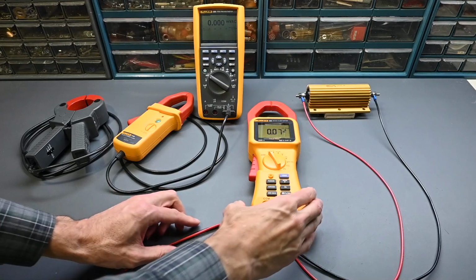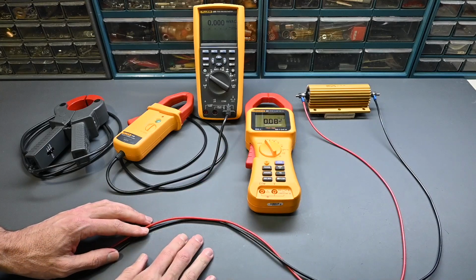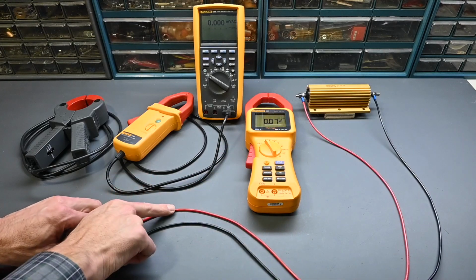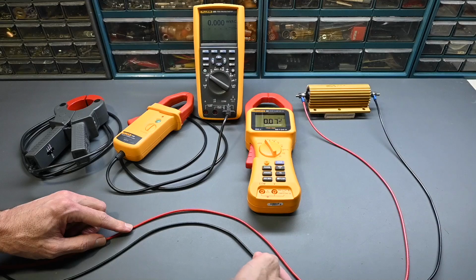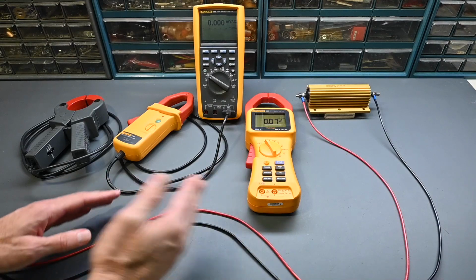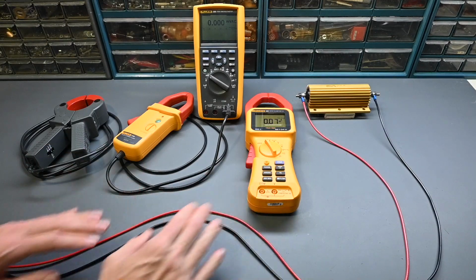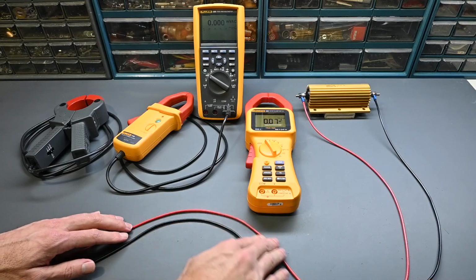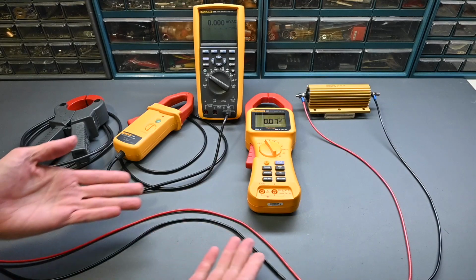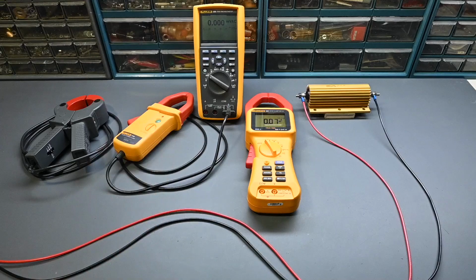Now the reason that the wires can't both be through the clamp at the same time is because when the current is flowing this direction on the red wire, it's going this direction on the black wire, because it's AC current, alternating back and forth. And the same thing would happen with DC current. If it's flowing in one direction on one wire, it's going the other direction on the other, and they essentially cancel out in the current clamp.